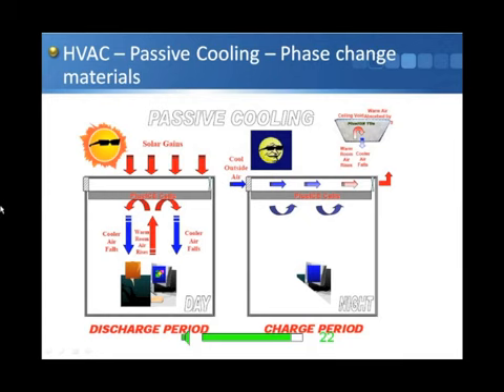So warm air rising from the desk during the day there is cooled and drops back down to keep the space under control, and then during the night air is brought in to refreeze those cells. When I say refreeze, this material is selected to freeze at a temperature we choose, typically in that application at about 24 to 25 degrees C, so the space below is maintained at about 21 to 22 degrees C.